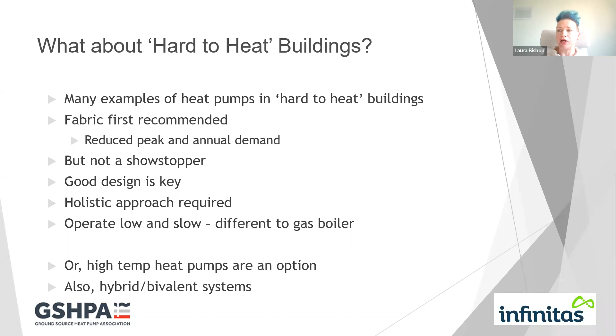You do have the options of high temperature heat pumps - we talked about those earlier, ammonia, CO2 heat pumps, going up to 75, 80, 85, 90 degrees. But of course your COP, your efficiency, will be hit. So if it's a very difficult building, you can still decarbonise, but you have to be aware of the impact on running cost. You can also look at hybrid and bivalent systems - I can go into that in more detail another time - which is coupling up things like ground source and air source, working out when it's more efficient to run one or the other, or even to still have gas boilers on as backup or peaking load.